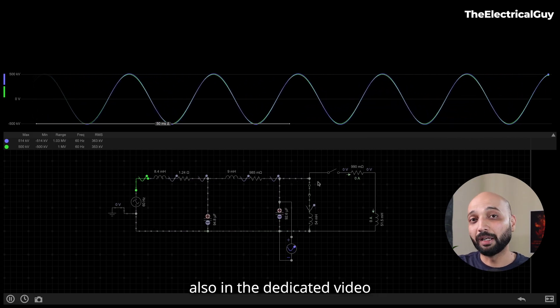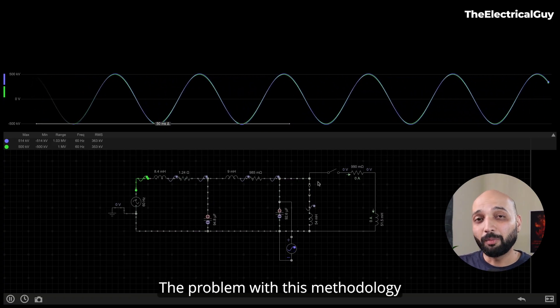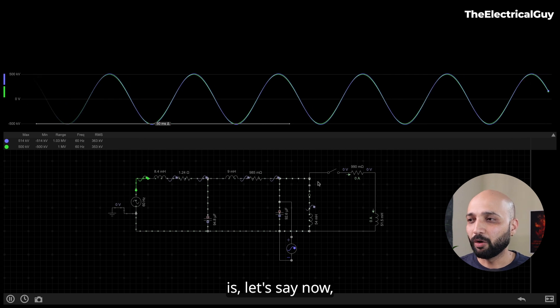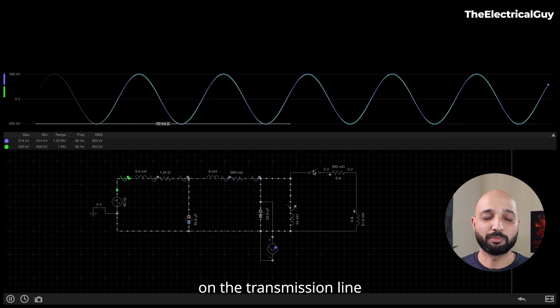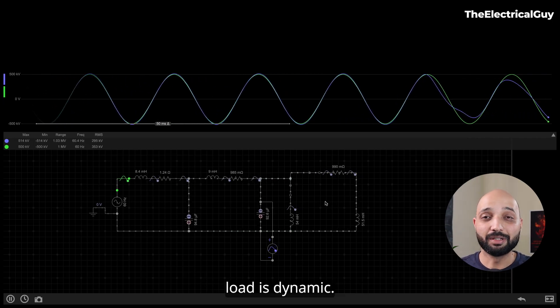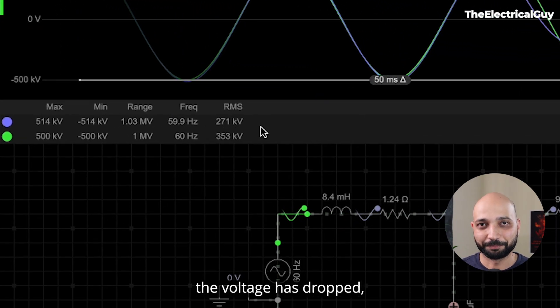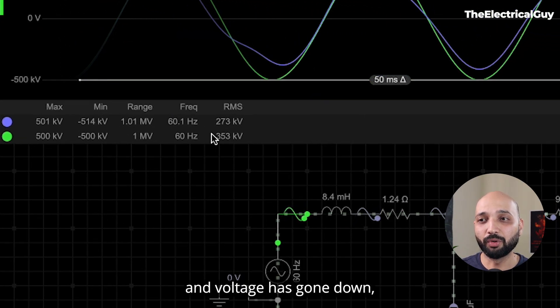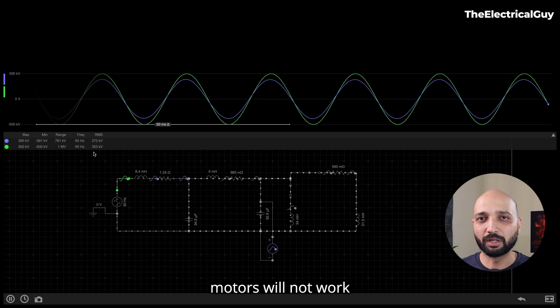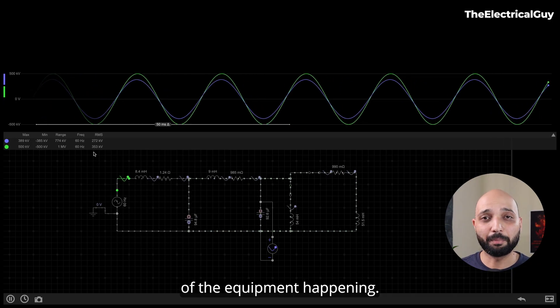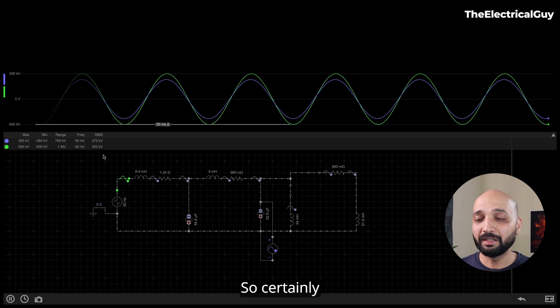We discussed this in a dedicated video on shunt reactors. The problem with this approach is that the transmission line load is dynamic — so if the shunt reactor stays in the system and load returns, the voltage drops. The receiving end voltage falls below the sending end voltage. This is also a problem because induction motors will not work correctly, there will be misoperation of equipment — both high voltage and low voltage are unacceptable.